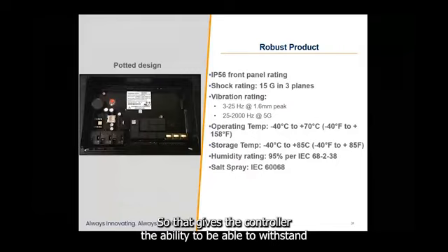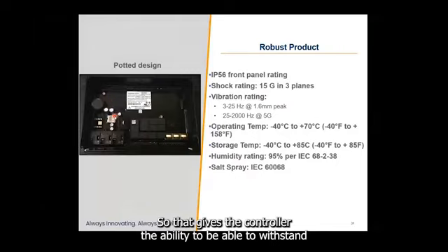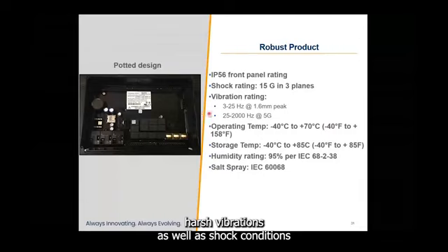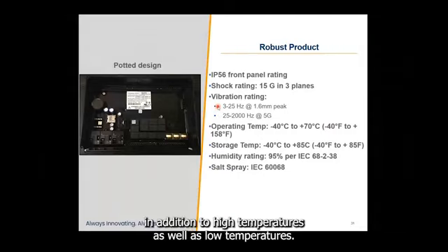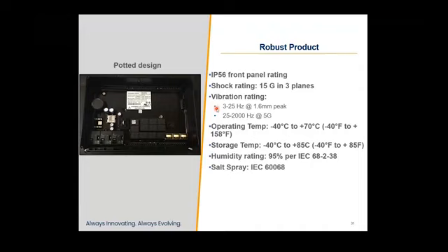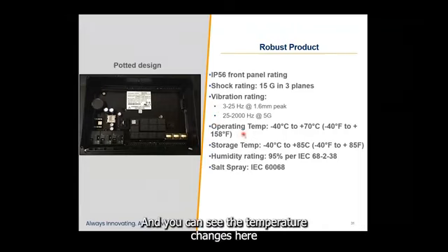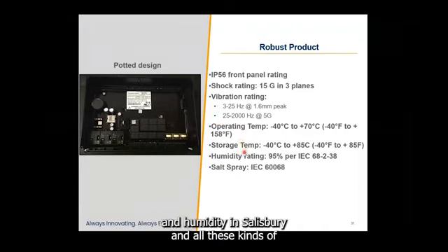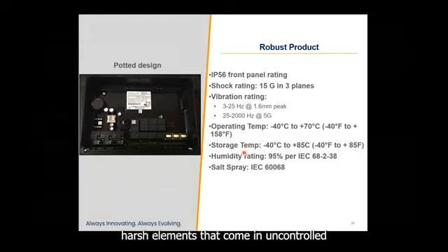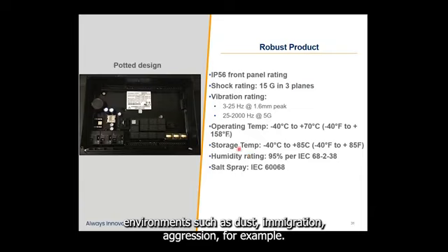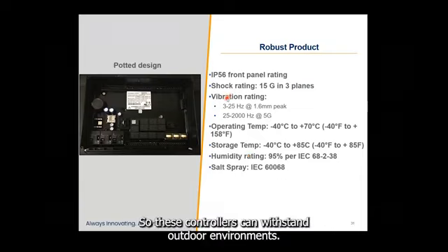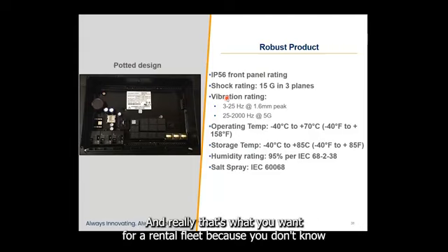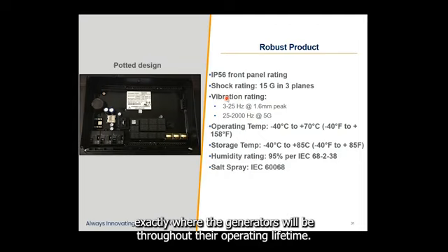So that gives the controller the ability to withstand harsh vibrations as well as shock conditions, in addition to high temperatures as well as low temperatures. And you can see the temperature ranges here, and humidity and salt spray and all these kinds of harsh elements that come in uncontrolled environments, such as dust ingression, for example. So these controllers can withstand outdoor environments, and really that's what you want for a rental fleet, because you don't know exactly where the generators will be throughout their operating lifetime.